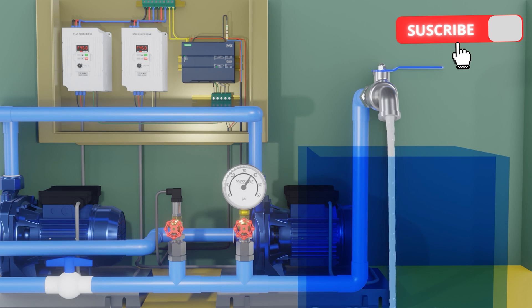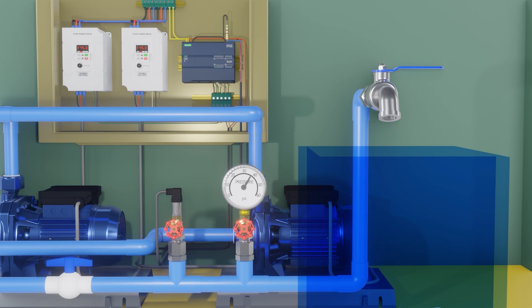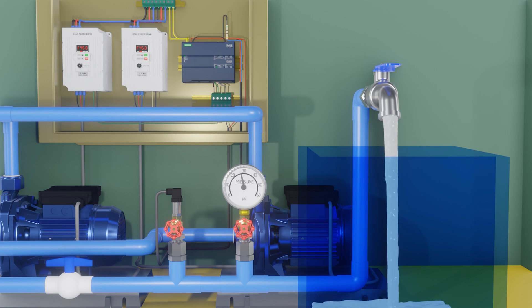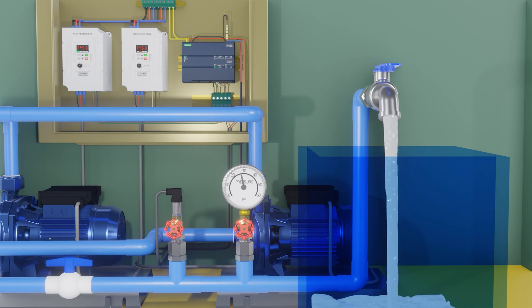We turn off the tap, and the pressure stops dropping. Now we open the tap completely. The pressure goes down. It reaches less than 30 PSI, activates frequency drive 1.